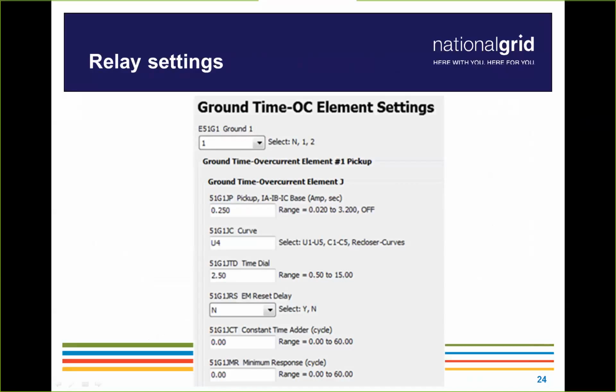There we go. Okay, so not a lot going on here. This is actually just a snapshot from a software program from one relay manufacturer. But for relay settings, if you have a separate relay, we would be very much interested in whatever relay functions are required. So in this one, there's some ground overcurrent pickup times and some time delays that we would be interested in seeing, those types of settings, what your pickup settings would be, what your delays might be. And so this is showing a snapshot from a single manufacturer's software for programming the relay.